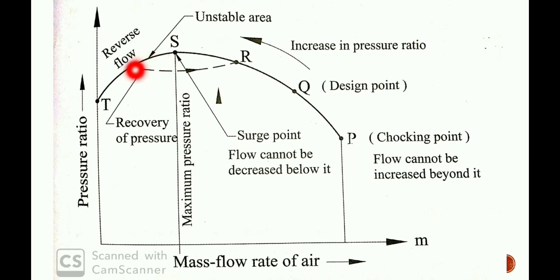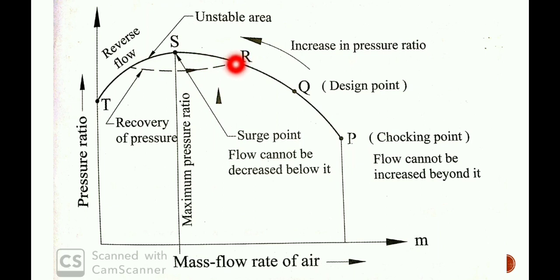Due to this backflow, accumulation in the receiver tank decreases. The compressor then starts to deliver air again. This cyclic process — backflow, pressure drop in receiver tank, compressor delivers again — is the instability of the compressor known as surging.